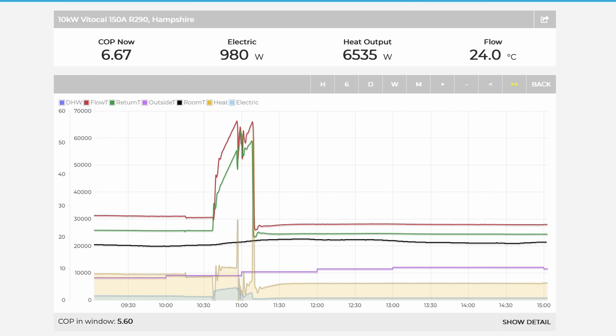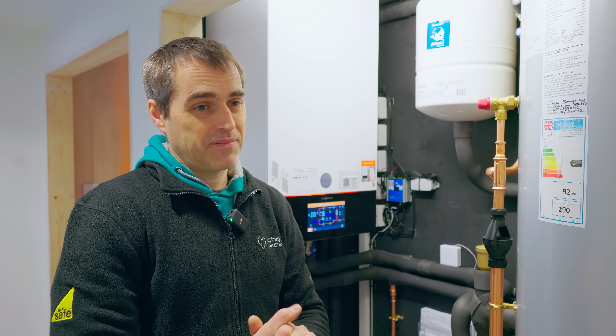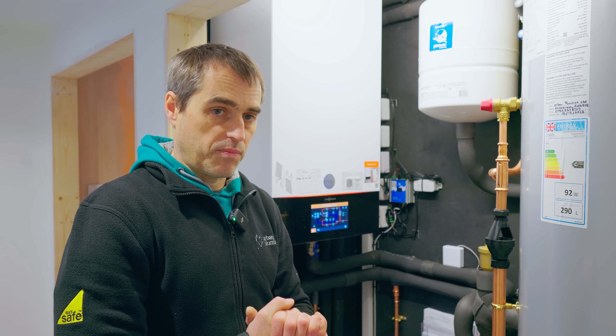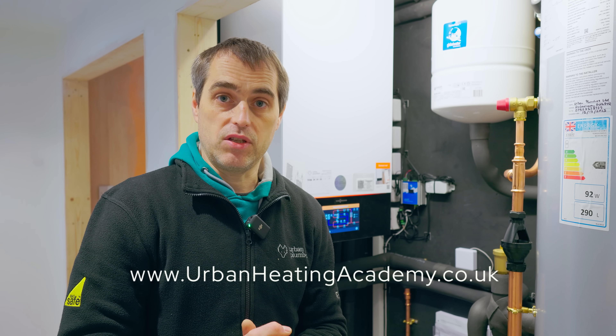My prediction is this is going to be in the top 5% of all systems in the UK. Simply because we've got underfloor heating on both floors, designed to a very low flow temperature — designed to 35 degrees, but I bet it's going to run much lower, probably top at about 30 to 32 degrees — and that will guarantee a heating COP of 5 or above. So: super simple, super efficient system. If you want to know how to design and install systems like that, we are preparing a heating installation and design mega course. Go to the link in the description and sign up to the waiting list to get early access at www.urbanheatingacademy.co.uk.